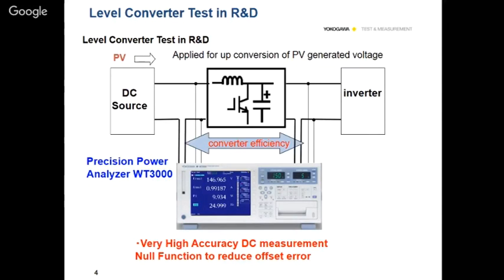What is the meaning of the null function, used to reduce offset error? Any test and measuring equipment has internal offset because it's electronic, consisting of many passive and active components, so it has its own offset, noise, or errors. The null function sets a reference point as zero, and from that zero you calculate the efficiency, giving one step ahead toward more precise calculation.